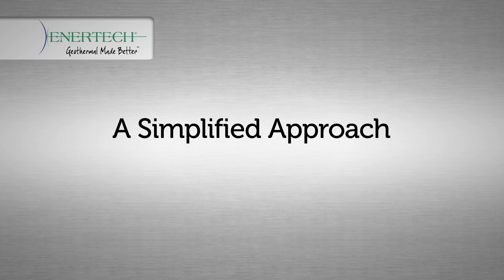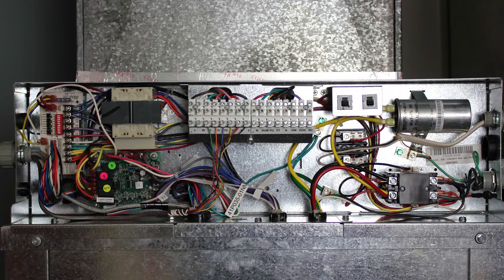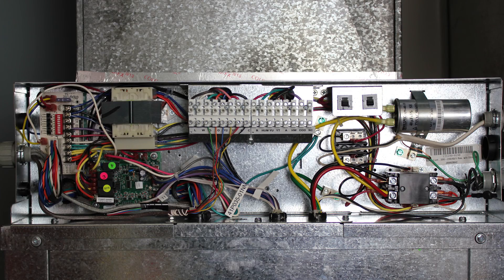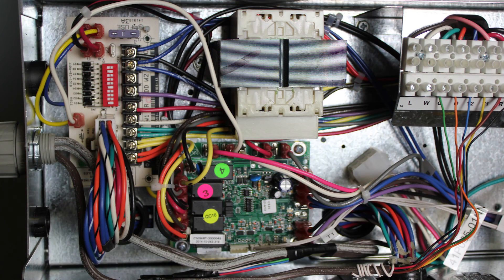Enertech's geothermal heat pump controls provide a modular approach for controlling the heat pump. It consists of one, two or three printed circuit boards depending on the features of a particular unit. This approach simplifies installation and troubleshooting and eliminates features that are not applicable for some units. A microprocessor based printed circuit board controls the inputs to the unit as well as outputs for status mode, faults and diagnostics. A status LED and LEDs for each fault are provided for diagnostics.